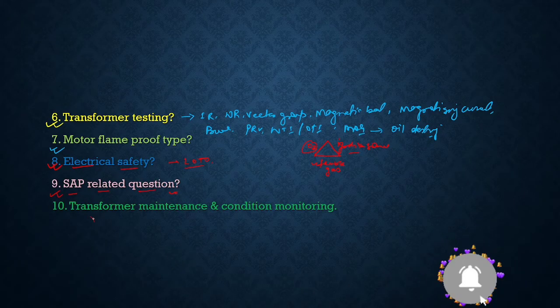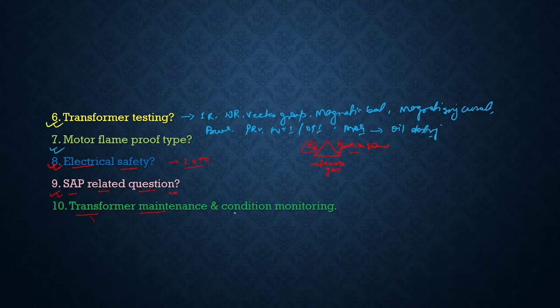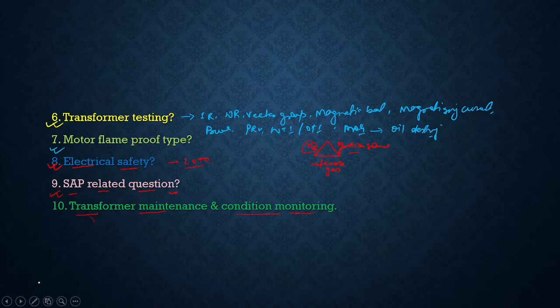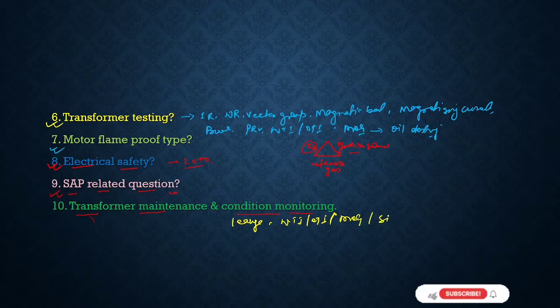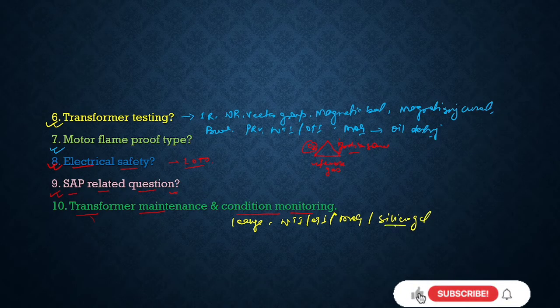The next question, like, what is transformer maintenance and what is condition monitoring? Since transformer is static equipment, and most of the time it is in running condition, all you need is to monitor the condition of the transformers. So what are the pre-checks that we do for transformer maintenance? You can say that you check any leakage, WTI temperature, OTI temperature, MOG, oil level. You will have a silica gel condition. So you can mention all those things for the monitoring of the transformer.